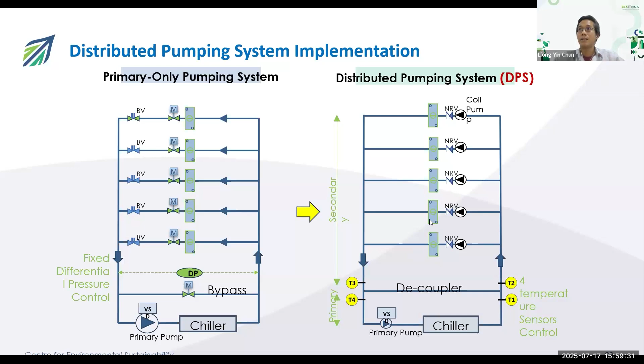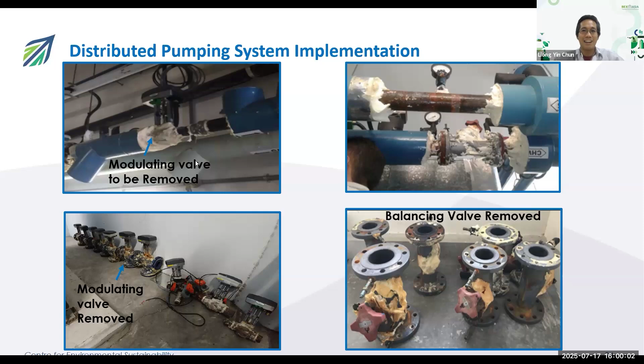All right, so this is the actual implementation. You can see that in this particular block, block 22, during the implementation, we removed all the modulating valves. We also removed the balancing valves in this case. It's a bold move. Imagine this is an operating building, and of course we have done many simulations before we do our job, to make sure that we have enough confidence to really retrofit the building in this way. And then we have the smart pump as well. We put in the smart pump to replace the location of the valve. So it's actually very nicely done.